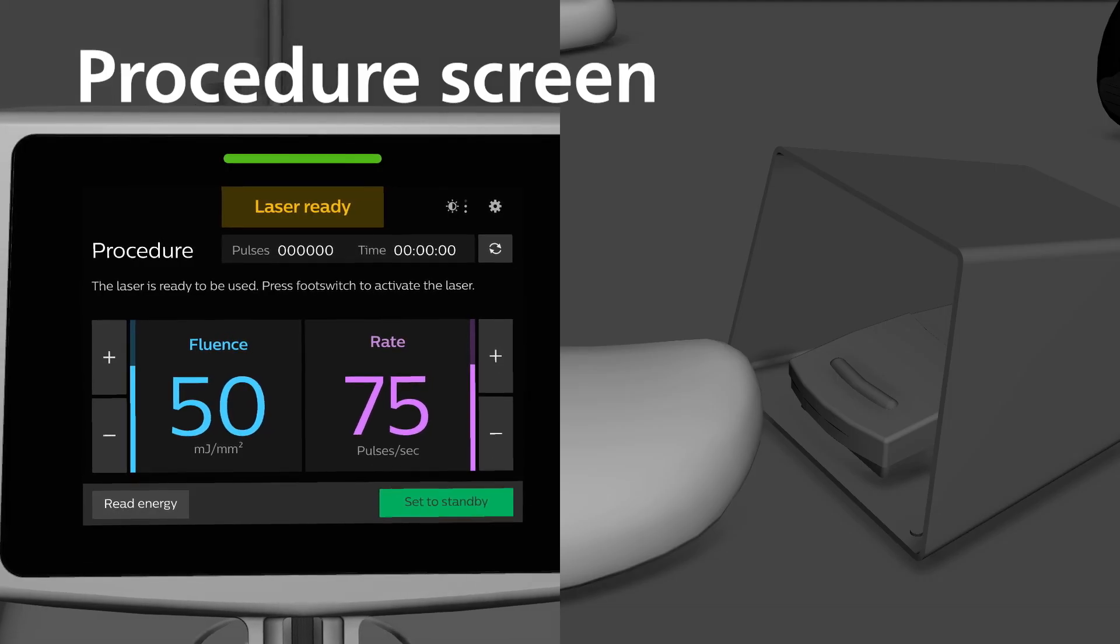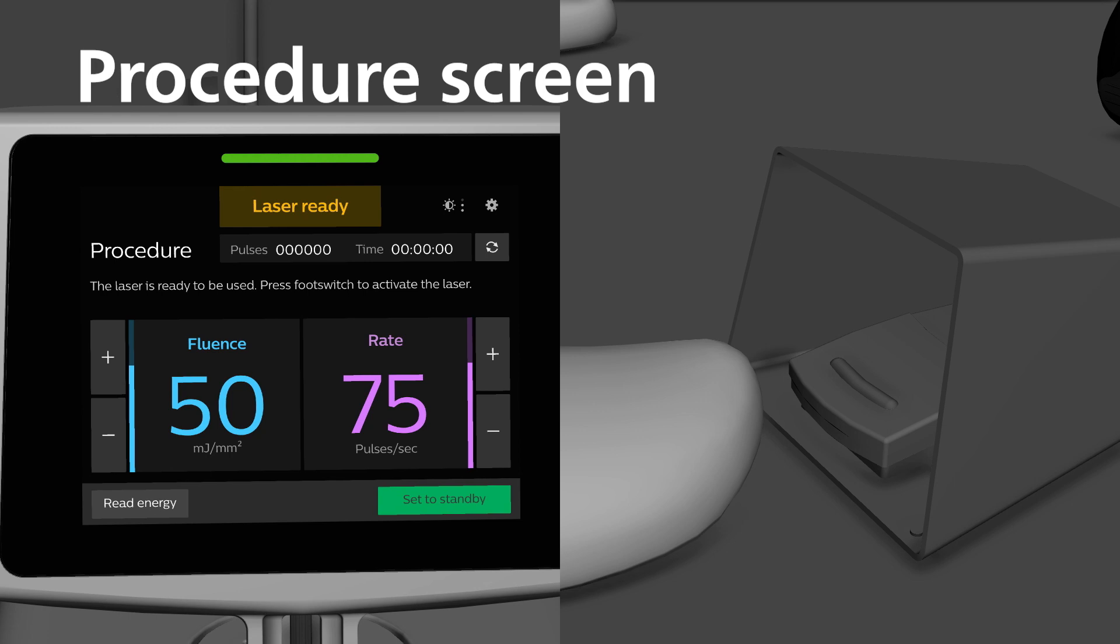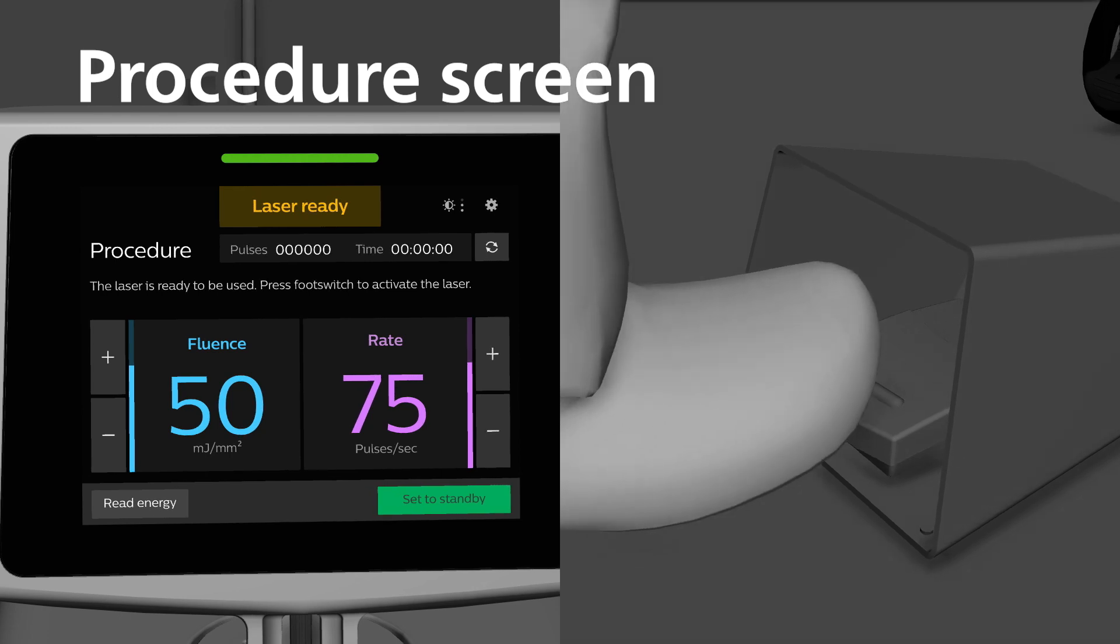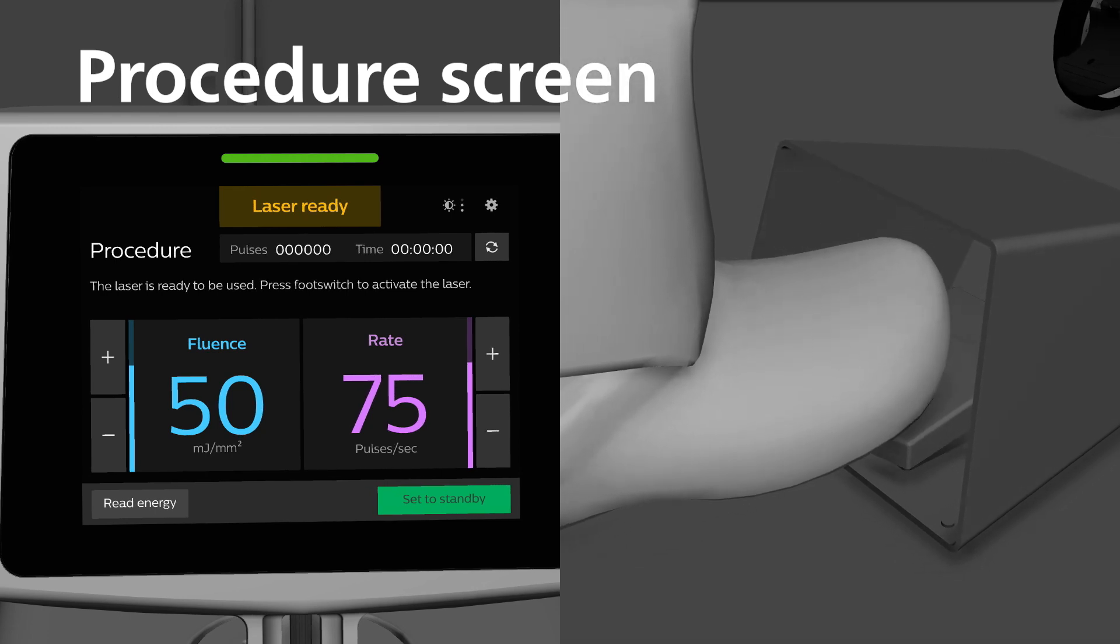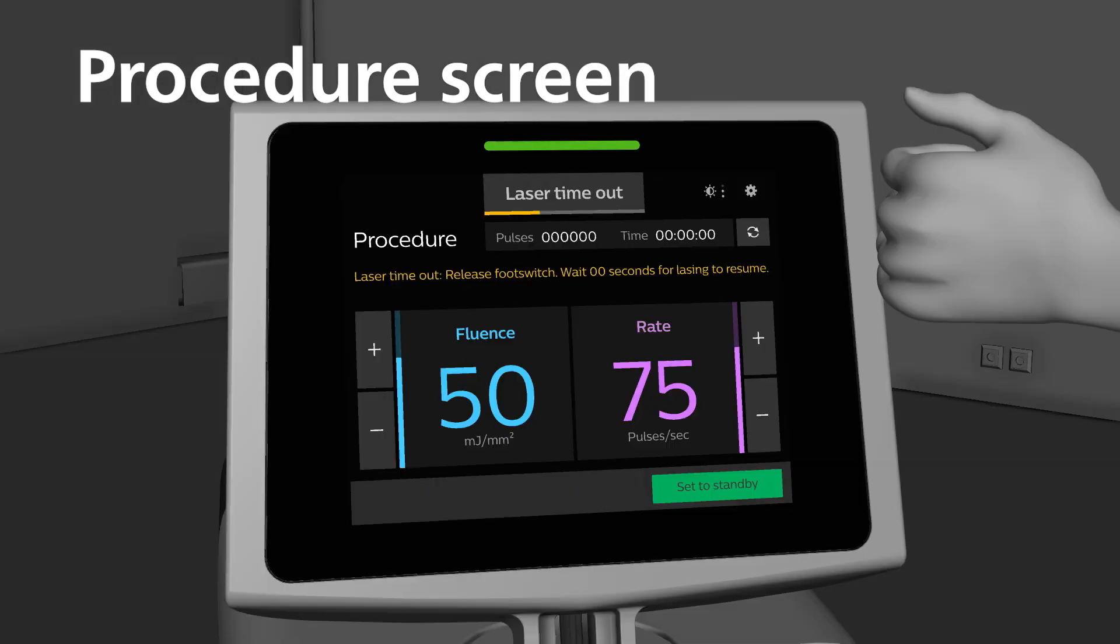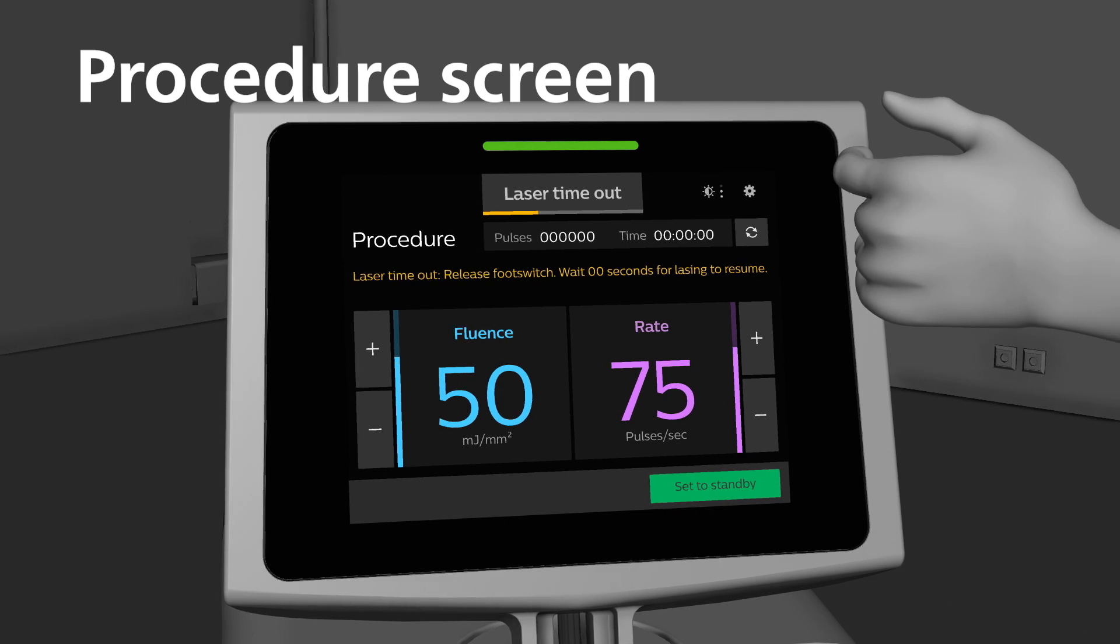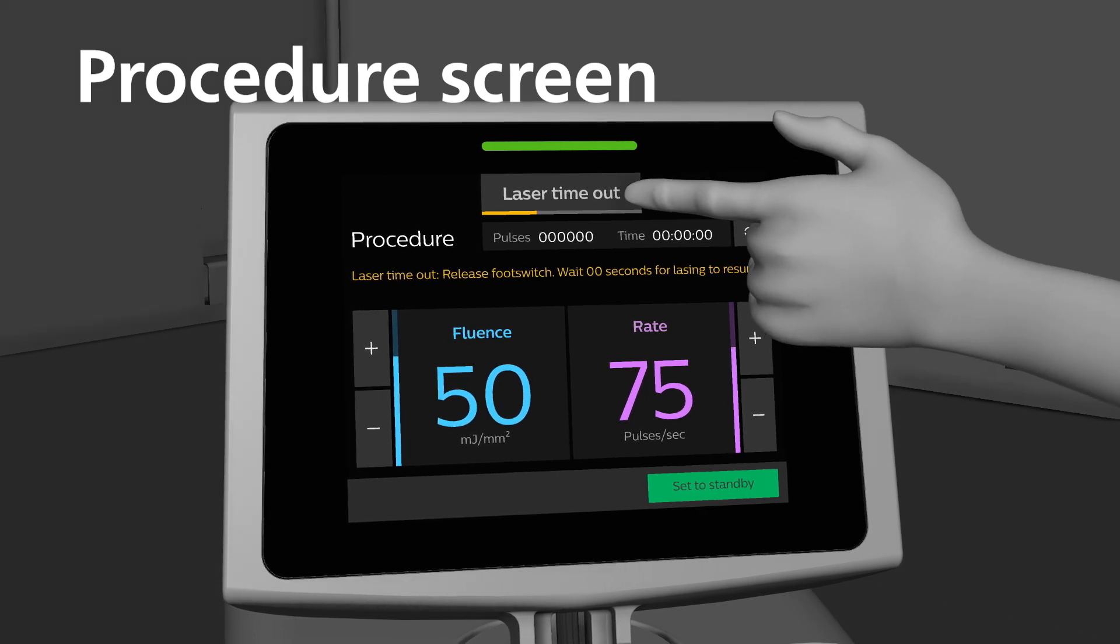While in Ready mode, the foot switch will be active. Once the catheter is in the desired location, depress the foot switch to activate the laser. If using a coronary or lead removal fiber catheter, there will be time-outs once you activate the laser. The system will provide a visual display of the remaining time left in the time-out. Once the time-out is complete, the system will provide audible feedback to notify the user.